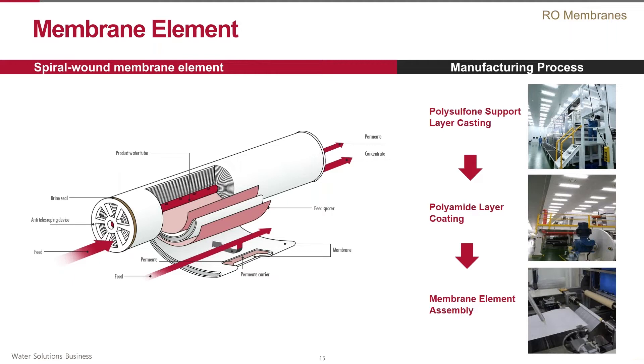The membrane leaves are separated by a feed spacer, which forms the feed channels and provides mixing of the feed stream along the length of the membrane element. The whole assembly of envelopes is rolled around the perforated permeate collector tube and covered by a fiberglass shell. The two ends of each RO element are finished with plastic cups called end cups or anti-telescoping devices.